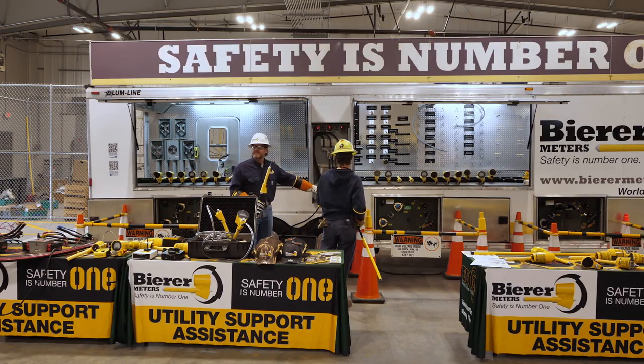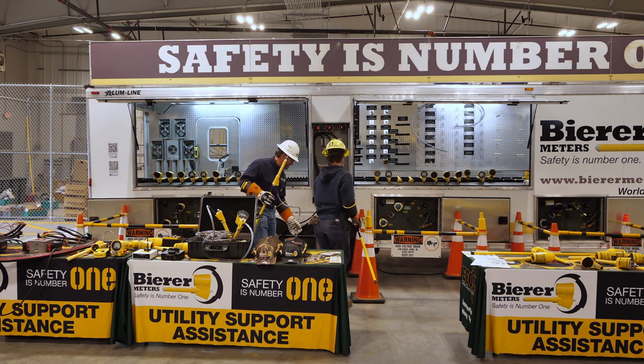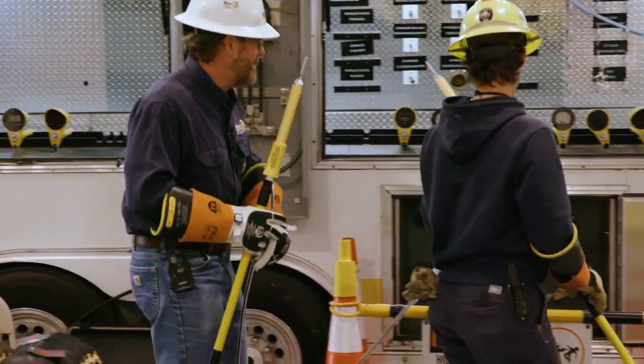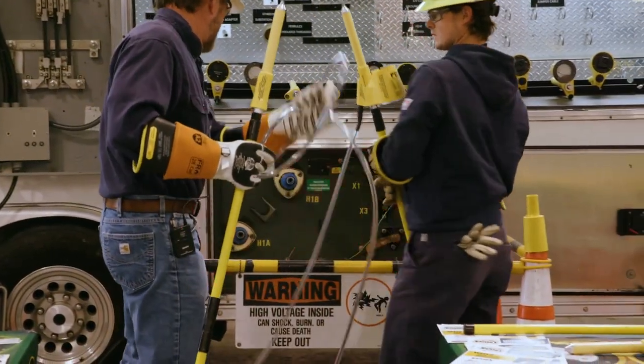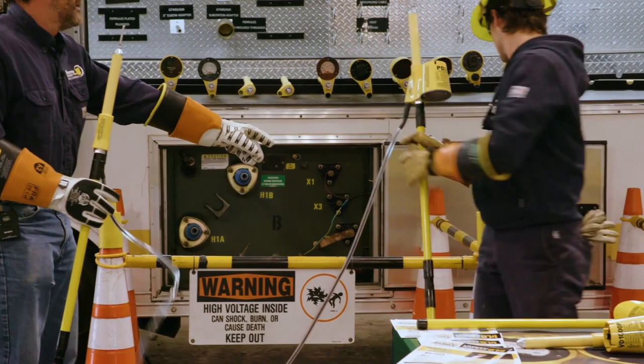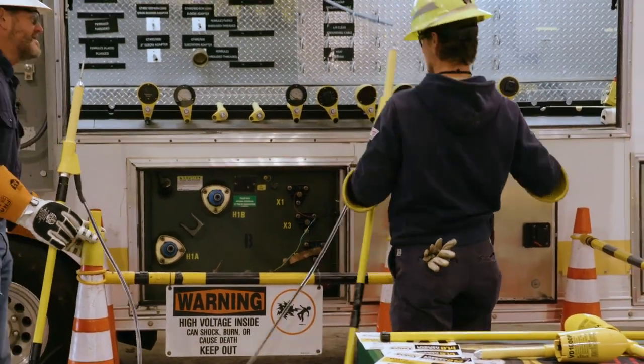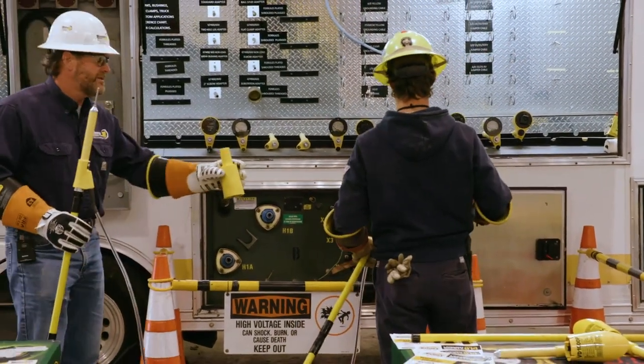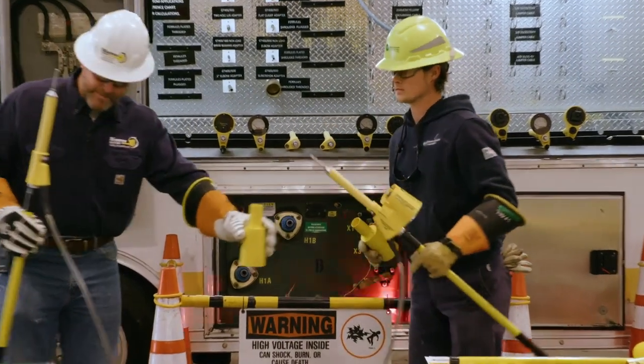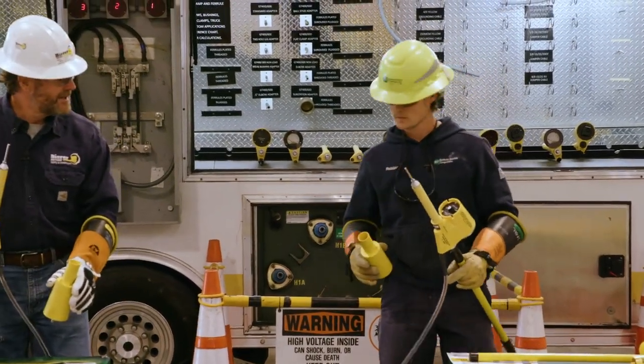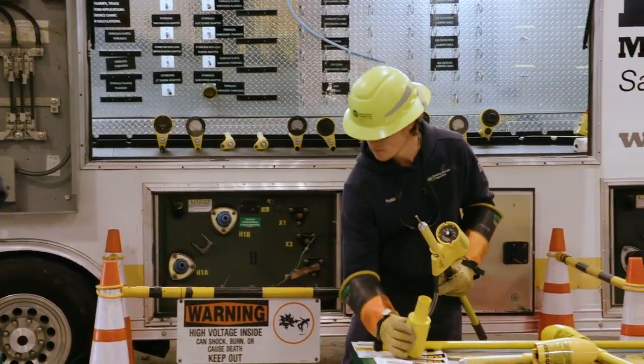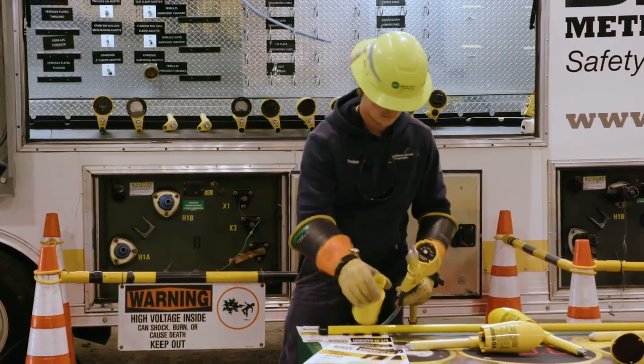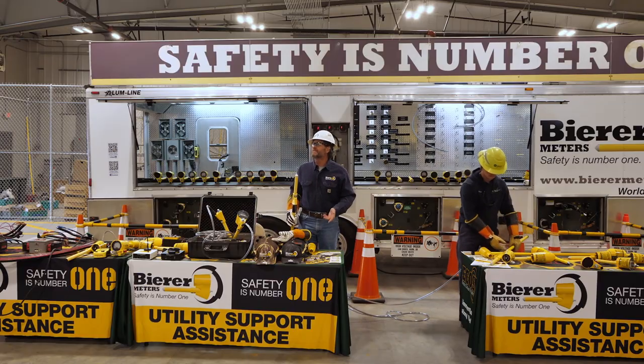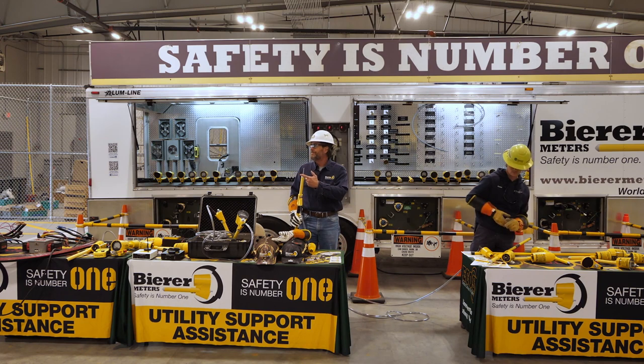Now we're gonna phase these hot bushings right here, we'll call it overhead line. We're gonna phase this, all right? Okay, come on. What you're gonna do, Robbie, is grab that bushing adapter that's on this cone, and take off the straight probe. Turn back around, walk a few steps, and we're gonna make the change here. So what we've done is make an accessory change off the cone tip.